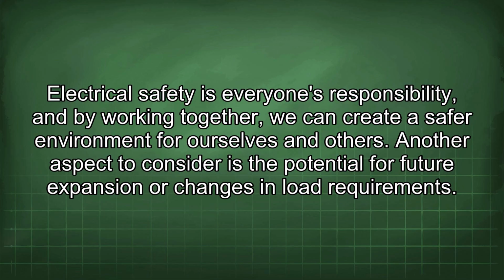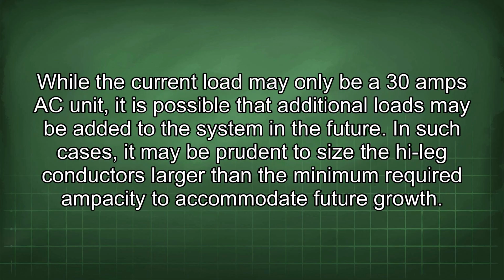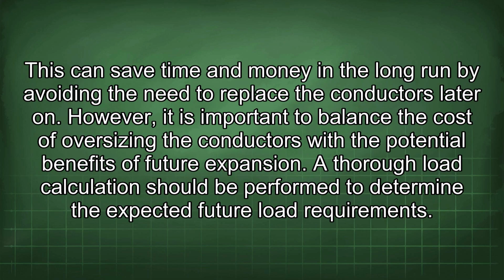Another aspect to consider is the potential for future expansion or changes in load requirements. While the current load may only be a 30 amp AC unit, it is possible that additional loads may be added to the system in the future. In such cases, it may be prudent to size the high leg conductors larger than the minimum required ampacity to accommodate future growth. This can save time and money in the long run by avoiding the need to replace the conductors later on.